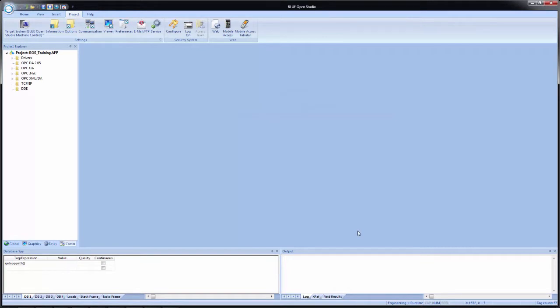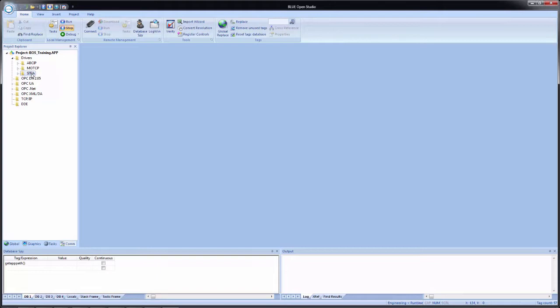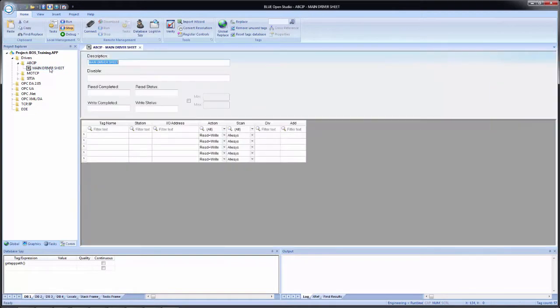And now what we want to do is close Blue Open Studio and then reopen. Because now if we go to com and we expand drivers, we now see two new drivers show up. The SITIA is there because I added a Siemens tag integration. The ABCIP is here because I added my ControlLogix 5000 integration.